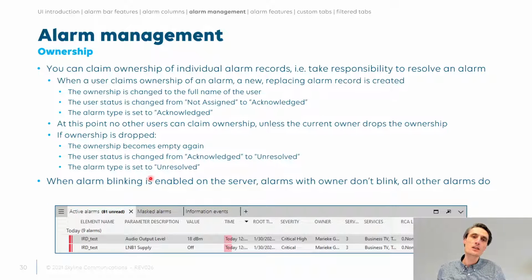And remember from the cube sidebar video that the alarm blinking, that is something which is by default not active in the DataMiner system, but you can activate that. If the alarm blinking is activated, all the alarms coming in will be blinking, will be flashing, the icon will be blinking there, until somebody takes ownership, and then the icon will be steady.